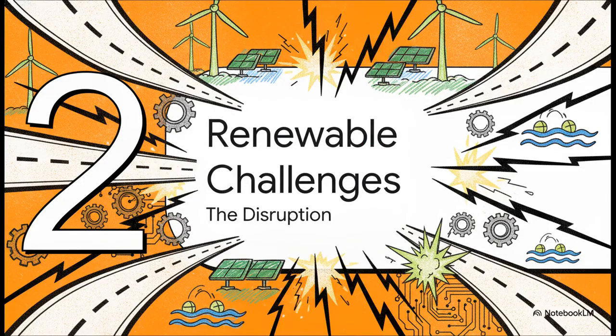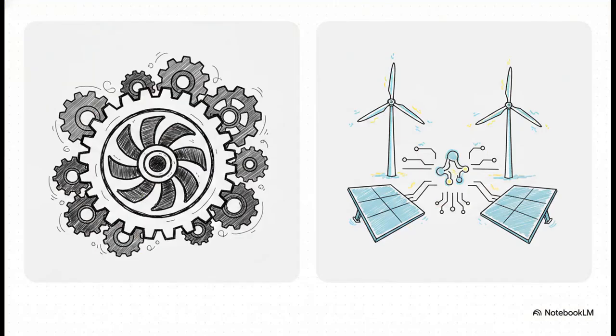Moving on to Section 2, the renewable energy challenge. This is where the disruption happens. Here is the absolute crux of the issue, the stark contrast between traditional synchronous generators and modern inverter-based renewables. Traditional systems were built around synchronous generators. Think of giant turbines spinning at a coal or hydro plant. They act like massive, heavy flywheels. They possess real, physical, mechanical inertia that naturally resists sudden changes in frequency.